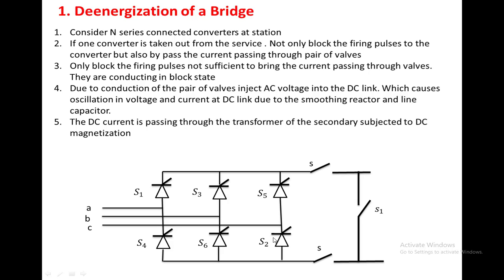Once the current is transferred from the conducting valve to the bypass valve, you then have to transfer it to the isolators. The two isolators are closed so that current is transferred to the isolator. Whenever the current is transferred to the isolator, no current is passing through the converter, and we can remove this converter from the string where N converters are connected.